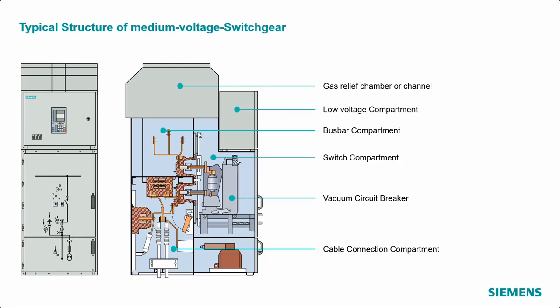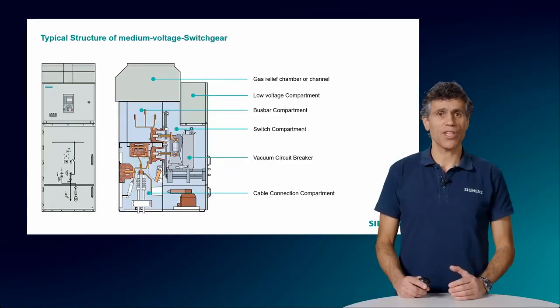You can see that there are different compartments in the switchgear. These compartments aren't all the same in all switchgear types. The compartmentalization is a very important characteristic of a switchgear because it allows different degrees of availability. If, for example, the circuit breaker has its own compartment, it can be accessible even when the other compartments are energized. If it doesn't, in order to remove it, for example for maintenance, you will have to switch off the power on the busbar and on the cable compartment before you access it.